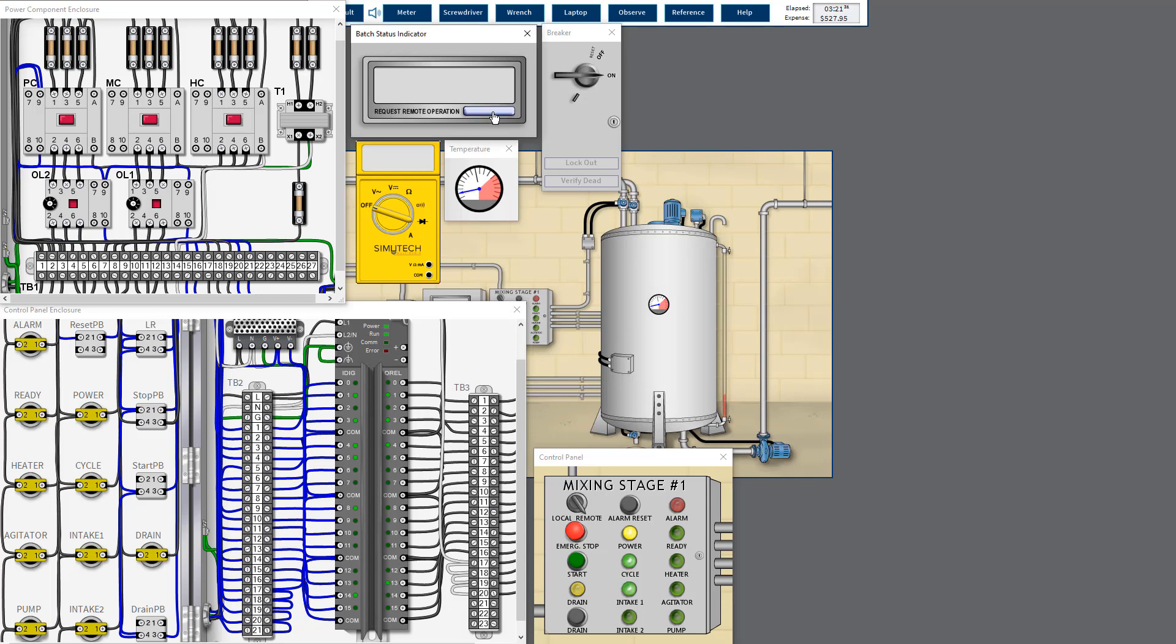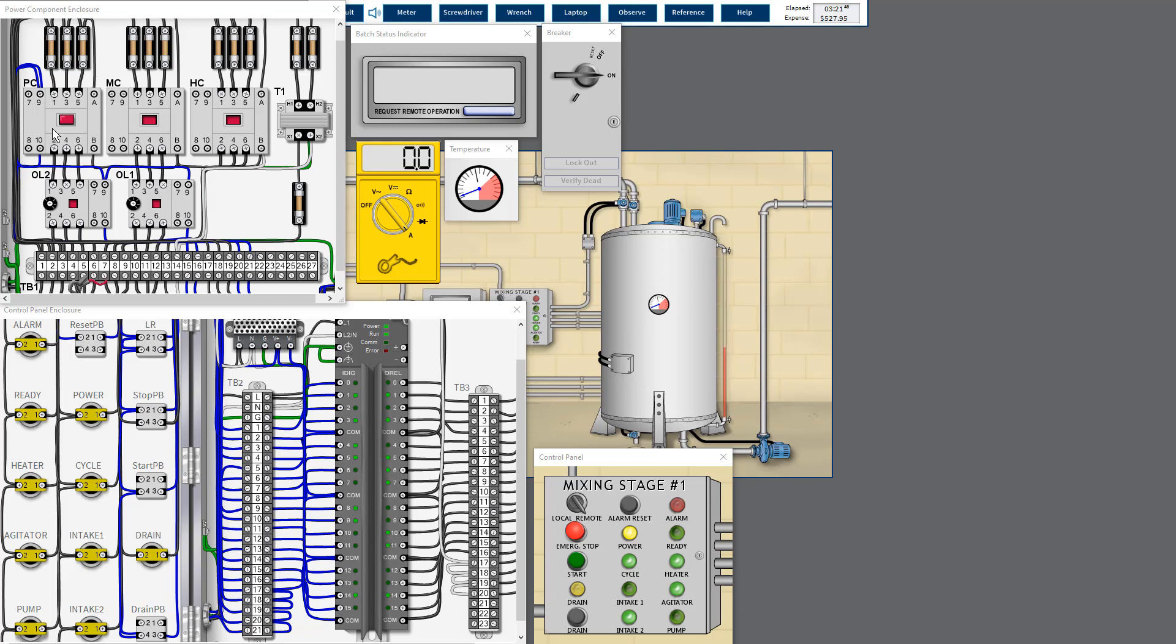And one more thing I need to remind myself is, if you see any problem here in the power panel, at the pump contactor circuit side, initially if we analyze further, there is an internally open circuit in one phase of the contactor. So initially it causes single phasing, and during single phasing where one phase is open, the motor will pull in a lot of current.